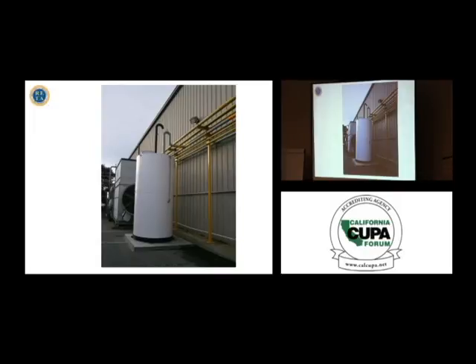So when I ran the numbers when we started building these for systems, 5/8 of it is for the standing water, and the 3/8 is the headspace to absorb what I expect it to receive and still keep it from spilling over. That's what we do. Also, we put an inverted P-trap here with a vacuum breaker there.